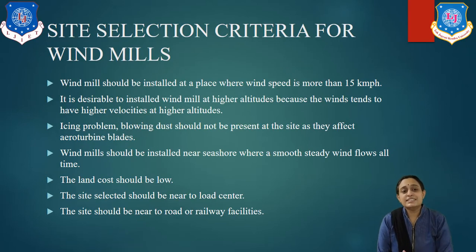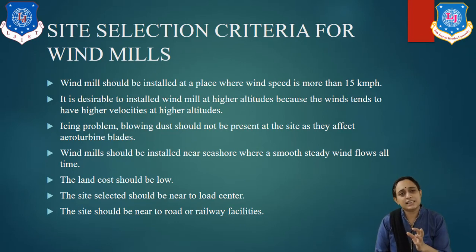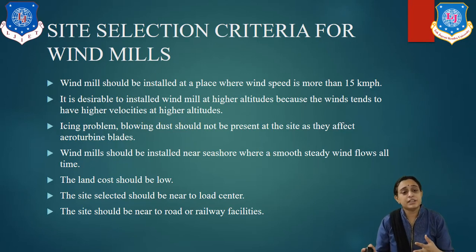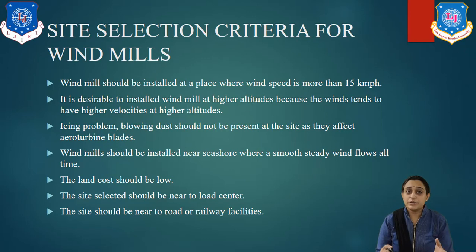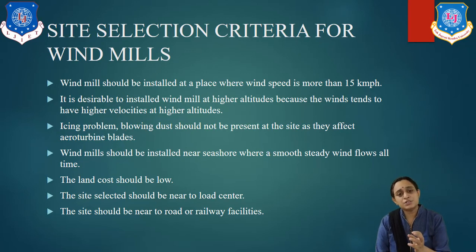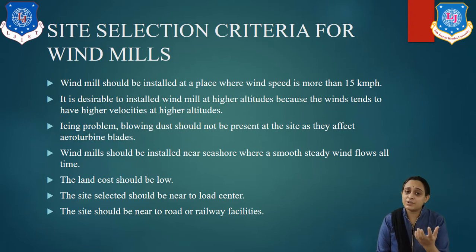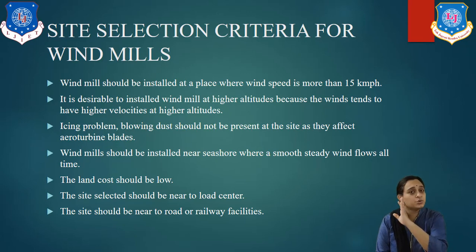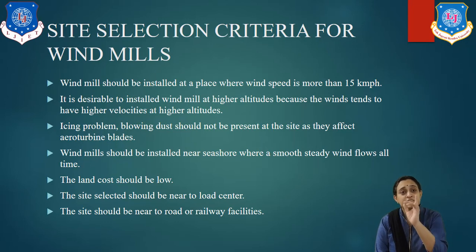Now we consider the site selection criteria for windmills, because the larger components require large space. The site selection is very important. A windmill should be installed at a place where wind speed is more than 15 kmph, which requires an open area. It is desirable to install a windmill at a higher altitude because wind tends to have higher velocity at higher altitudes. We have already studied that from 10 m to 200 m height, velocity V is proportional to height to the power of 1/7.